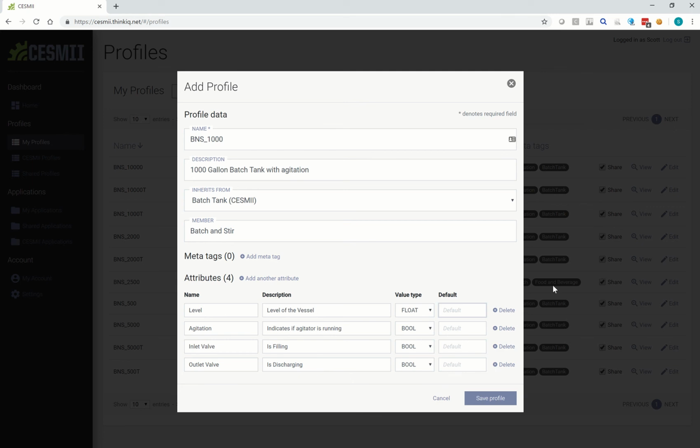And so the idea on this is we could put an appropriate path in here that a software vendor's application would be able to resolve back to the controller address. And some of that is dependent on the software vendor's application and how it makes connectivity to that data. But in this case, we're just going to address this like 192.168.1.1:level. And I'm going to copy that because that's going to be pretty close to right for the rest of this.